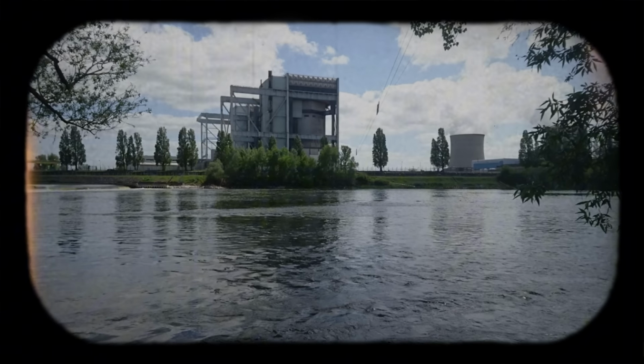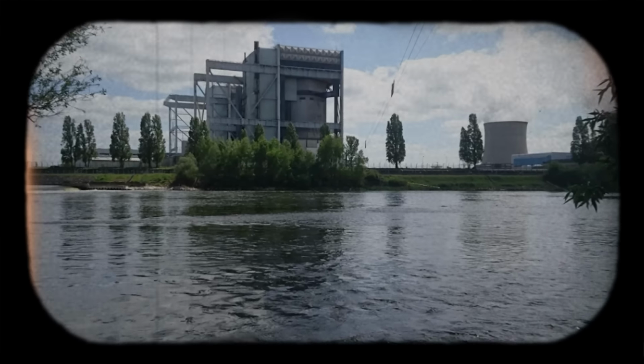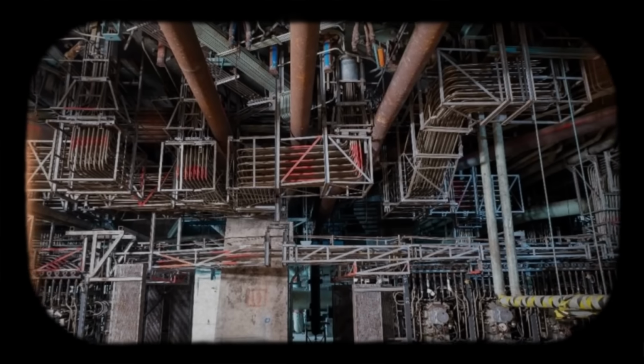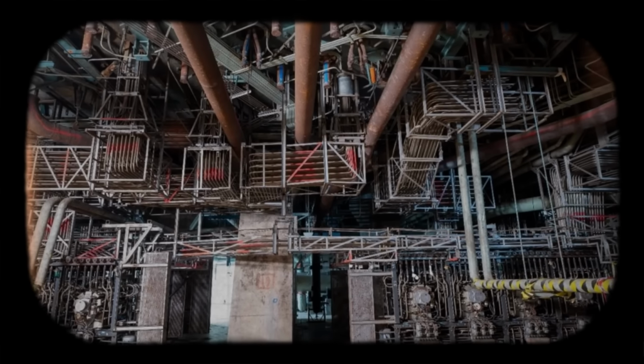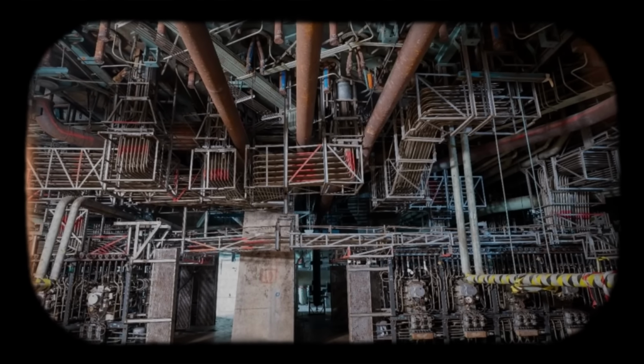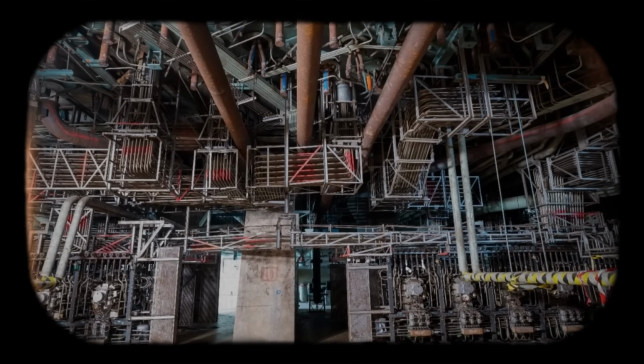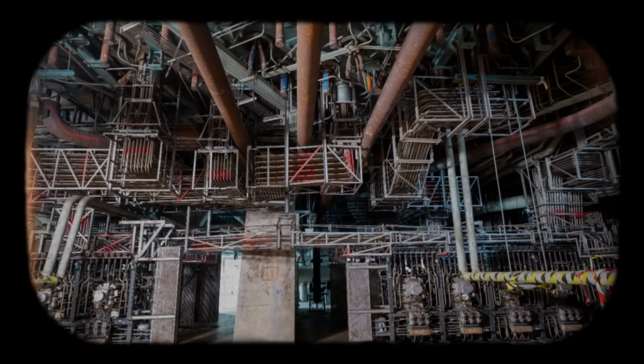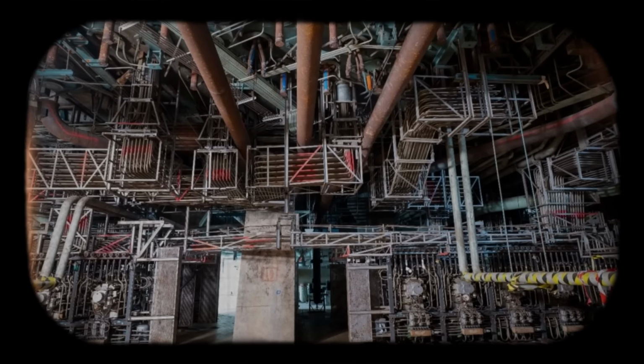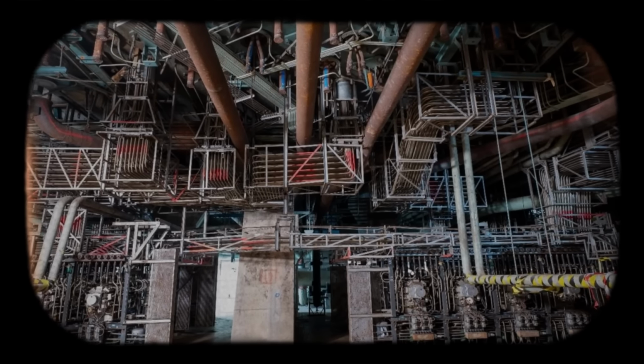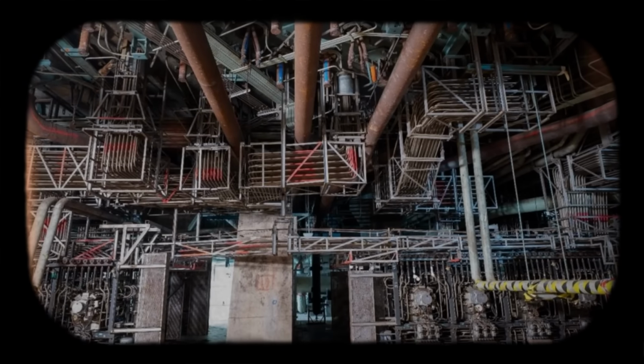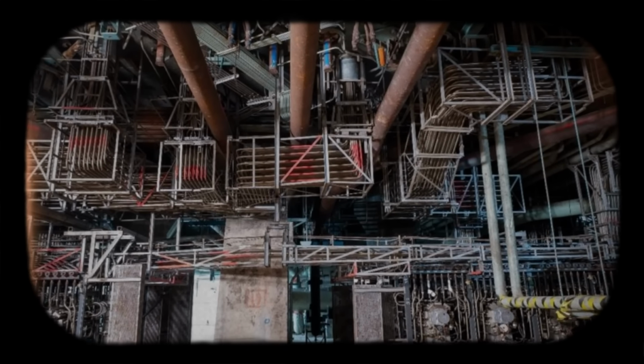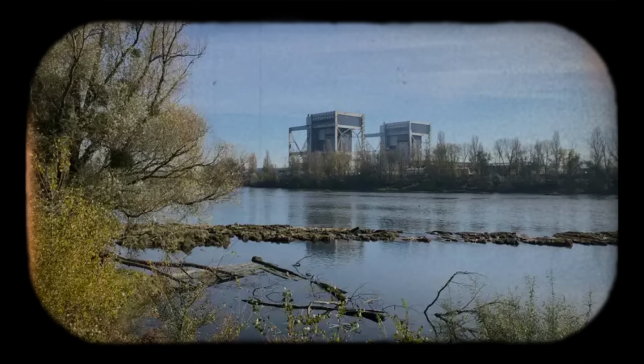Online refueling distinguishes UNGG technology from earlier reactor designs that required shutdown for fuel changes. The charging machine stores up to several dozen components in internal chambers, each indexed by the control program. A typical fuel channel operation involves removing spent elements, inserting fresh fuel, and adjusting graphite plugs or flow restrictors to fine-tune coolant distribution across the core.